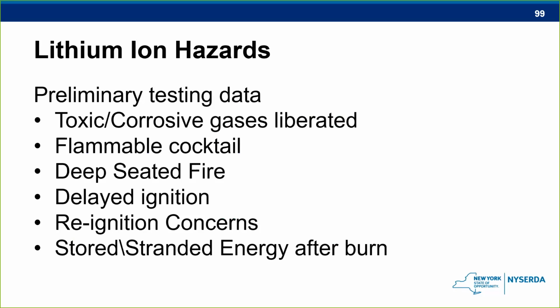So that's a very real concern for the firefighters, which brings us back to the fire remediation team and how Jennifer said the firefighters do not want to sit on this thing all night long waiting for this thing to go on fire again if it does go on fire. So what they're going to do is they're going to have that handoff procedure, and that's something that you may require in your jurisdiction. And then last but not least, we still have that stored and stranded energy even after the burn. After the burn, that energy does not dissipate. It could, but there's a chance that it doesn't. So we always like to tell the firefighters, always consider that thing charged and it still has energy inside of it. Next slide, please.